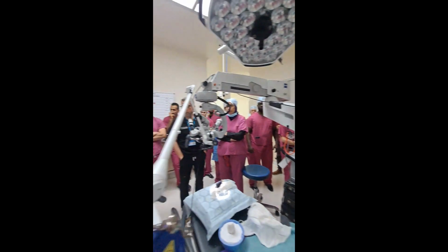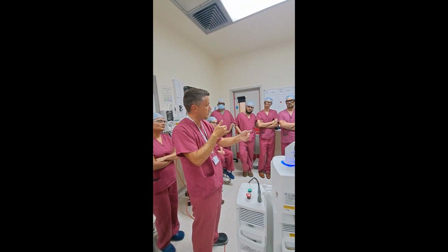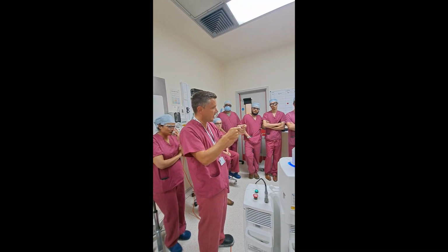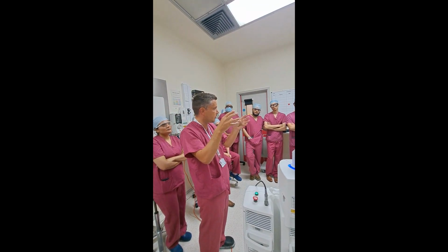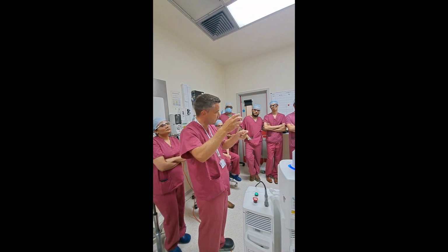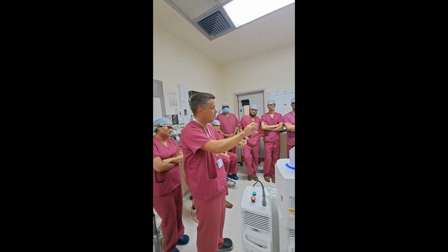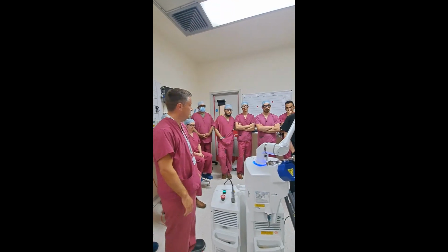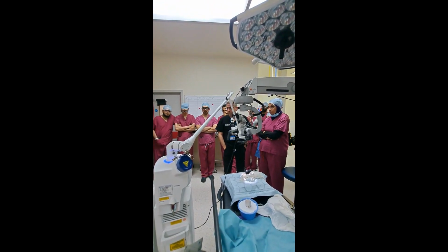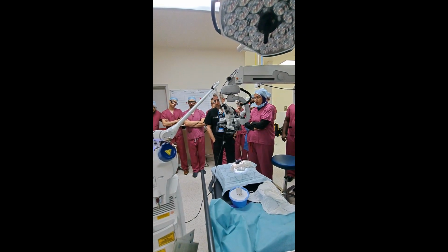There's another clue, an audible one. When the laser is focused properly, you will hear a buzzing noise on tissue, and it will just cut clean with no charring. If you're getting charring and more necrosis, and you're not hearing a nice buzzing noise, you should make a micro adjustment, either by physically moving the microscope in and out, or on the focal group. So you've got a few different clues to know whether it's optimized or not. You should be able to see those either on tissue or on the piece of wood.